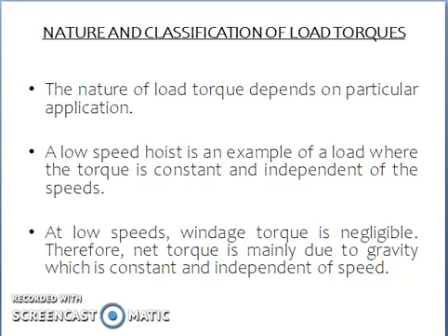Further, fans, compressors, aeroplanes, centrifugal pumps, coilers, traction, etc. are examples of cases where load torque is a function of speed. In a fan, compressor and aeroplane, the windage torque dominates, which leads to the load torque being proportional to the square of the speed.